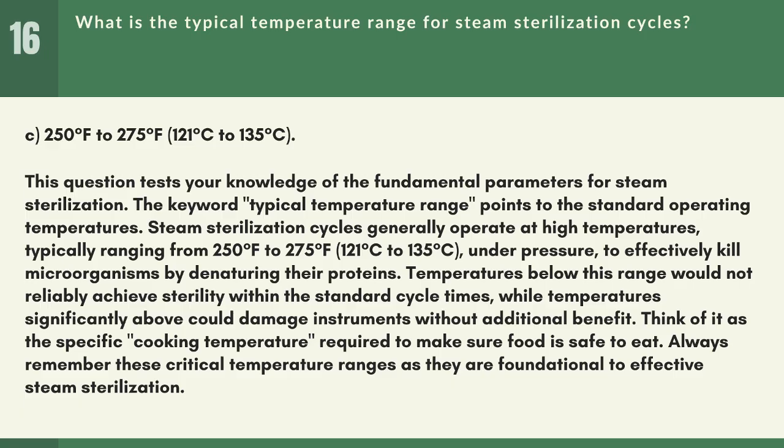Temperatures below this range would not reliably achieve sterility within the standard cycle times, while temperatures significantly above could damage instruments without additional benefit. Think of it as the specific cooking temperature required to make sure food is safe to eat. Always remember these critical temperature ranges as they are foundational to effective steam sterilization.